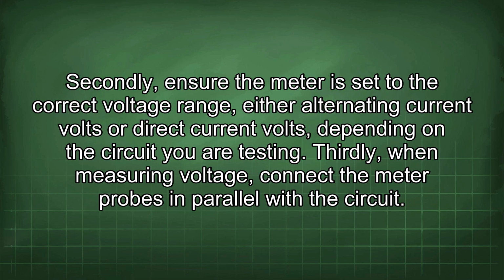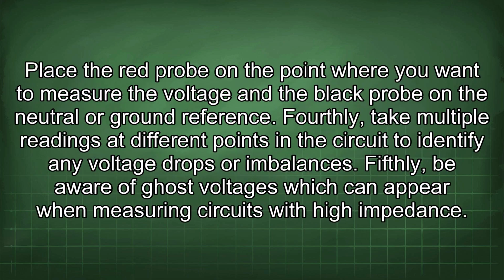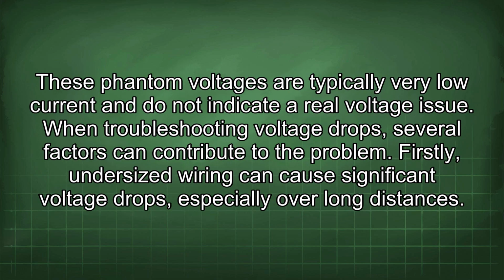Thirdly, when measuring voltage, connect the meter probes in parallel with the circuit. Place the red probe on the point where you want to measure the voltage and the black probe on the neutral or ground reference. Fourthly, take multiple readings at different points in the circuit to identify any voltage drops or imbalances. Fifthly, be aware of ghost voltages which can appear when measuring circuits with high impedance. These phantom voltages are typically very low current and do not indicate a real voltage issue.